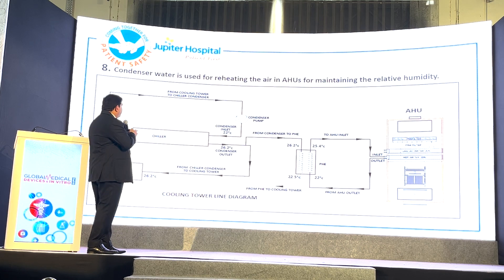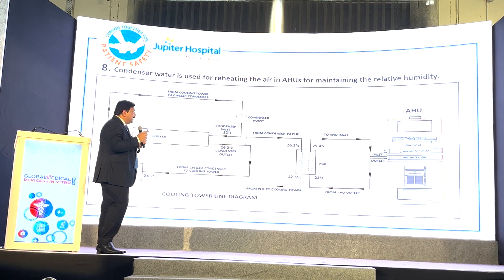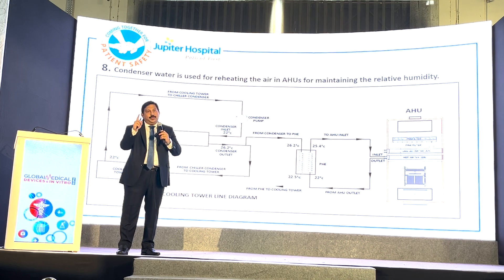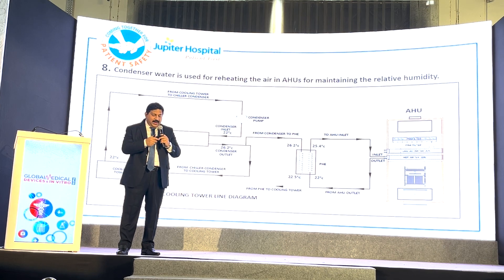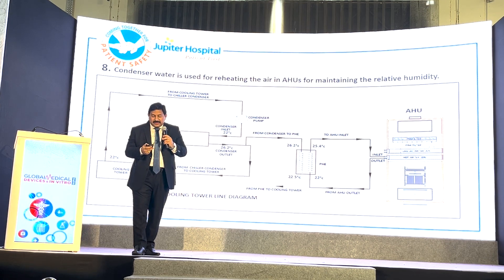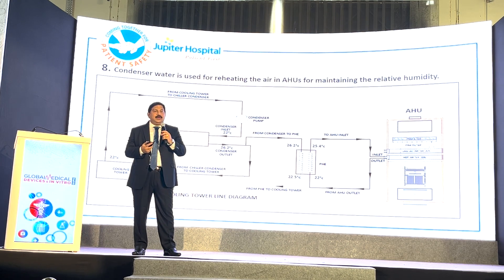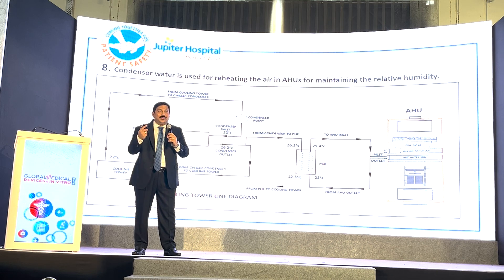For medical equipment, other than temperature, one important factor is humidity — humidity has to be below 60%. I am making one point you will always remember: I am from the medical engineering side. All the companies — CT scan, MRI, cath lab, linear accelerator — they always say we need to maintain a temperature of 22 degrees.